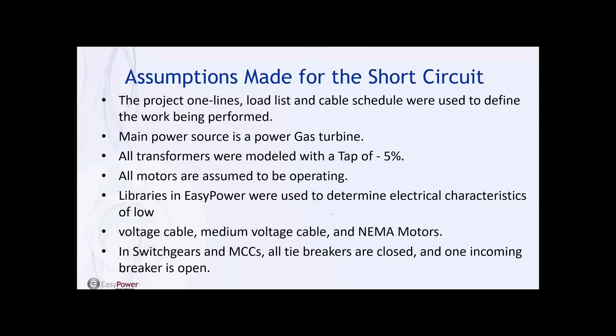Remember, if we have both incoming breakers closed and the tie breaker closed, the short circuit is twice as high because the power transformers are in parallel, therefore the impedance is in parallel. So this scenario is not possible, it's too high.